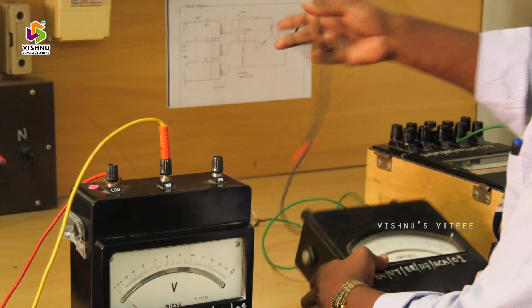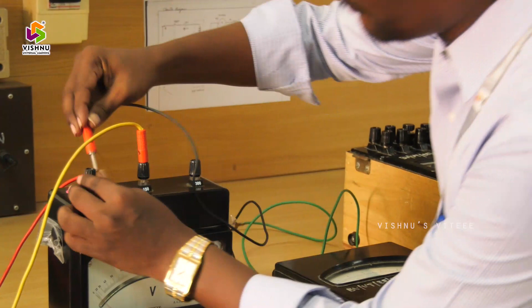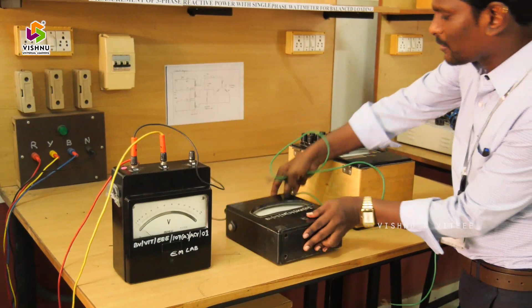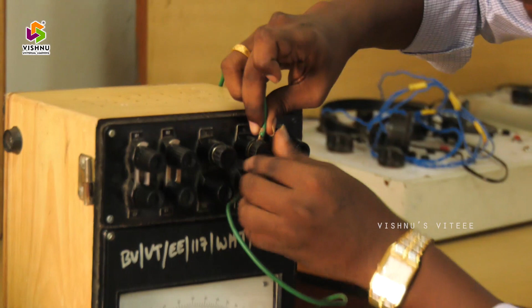Now similarly, the ammeter is connected in series with the R phase. This is the ammeter and this is the R phase. The red wire is already available here, so from this point we connect to the ammeter common. So the ammeter is connected in series with the R phase. One terminal of the ammeter is connected to the supply, and the other terminal is connected to M, the main terminal of the wattmeter. This is M, the main terminal of the wattmeter.